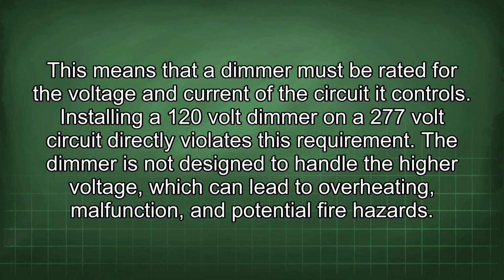Installing a 120-volt dimmer on a 277-volt circuit directly violates this requirement. The dimmer is not designed to handle the higher voltage, which can lead to overheating, malfunction, and potential fire hazard.